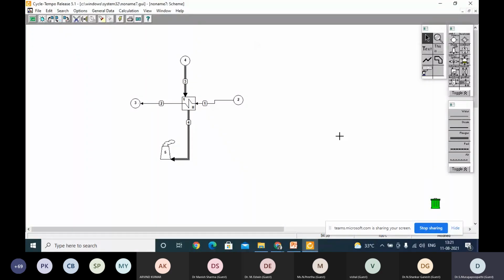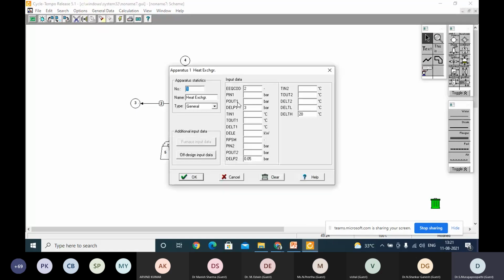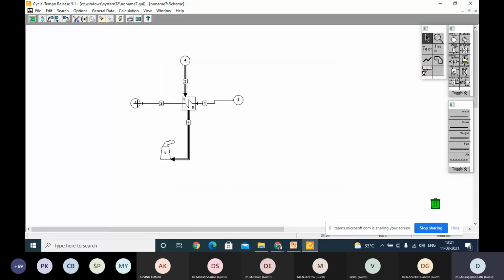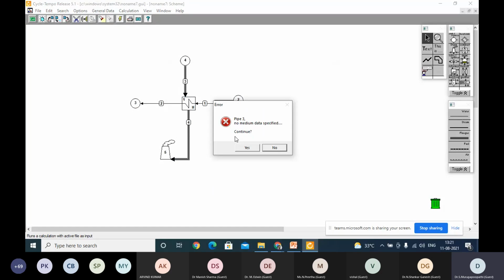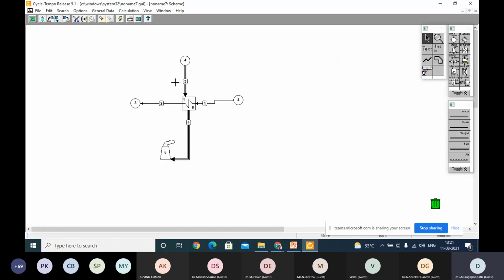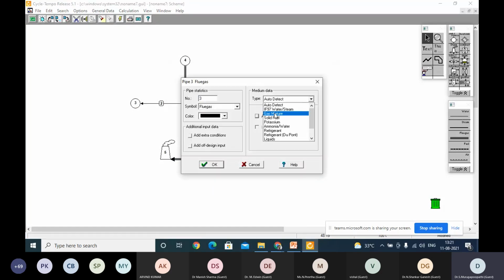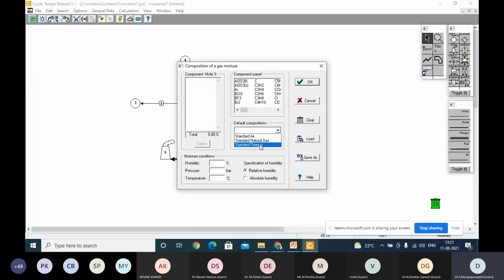So these data are sufficient. No need to give any data for the stack point, because we have specified the conditions for the heat exchanger, and also for the sink, in the heat exchanger. We can just run it. Here there is no medium specified, so you have to specify the medium - gas mixture and add the composition, which is standard flue gas.